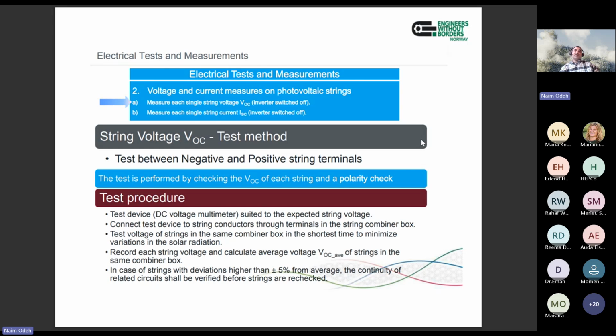Doing the VOC test for the string is the same as doing it for a single module. You need to check visually that all MC4 connectors are properly connected for the full string, and then you can use a multifunction meter that supports the expected voltage rating. Here, with 20 modules of 50 volt connected in series, the expected voltage will be around 500 volts, so you need a multifunction meter that supports such a rating. Once you have the full string connected, connect positive to positive, negative to negative, and then test the voltage.